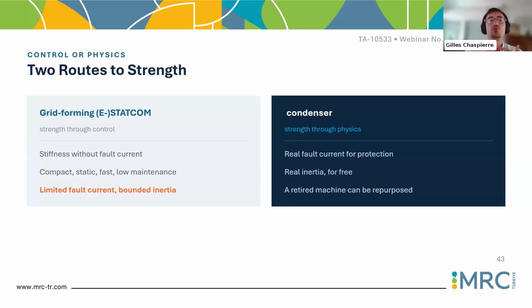So it's not okay. You need to move to what we call eSTATCOM, where you will have oversized capacitors to store the minimum amount of energy to make sure the asset can work properly in grid forming mode and provide fast voltage controllability. Then we discussed also the synchronous condenser, a completely different technology, rotating masses, very similar to a synchronous generator, providing real inertia. So if you need a big amount of inertia, maybe better to go for a condenser, and it can provide high fault current.